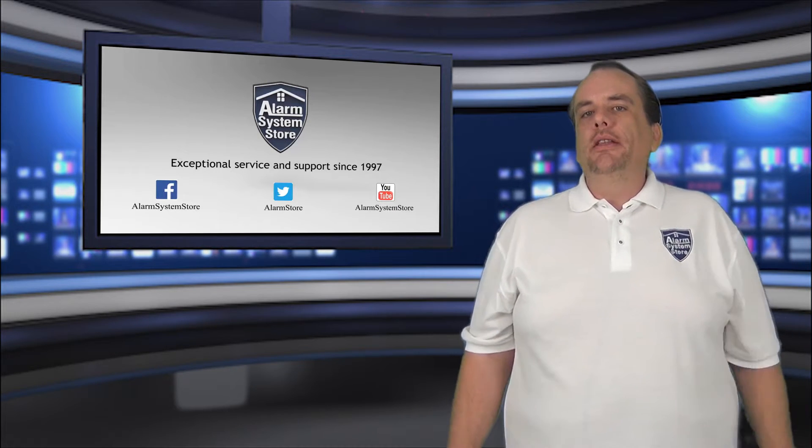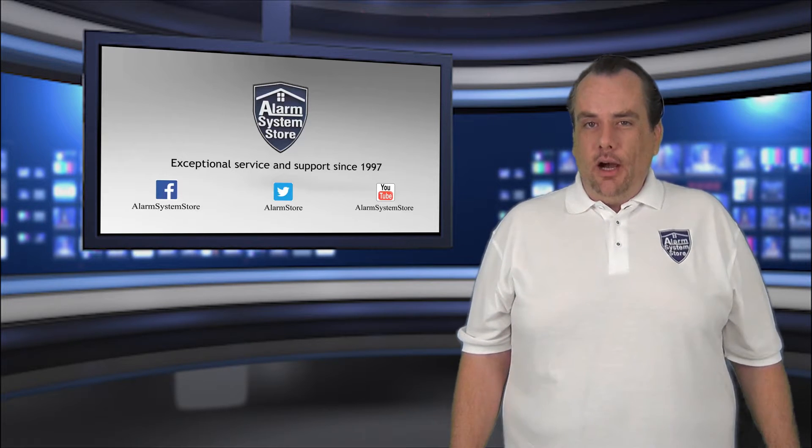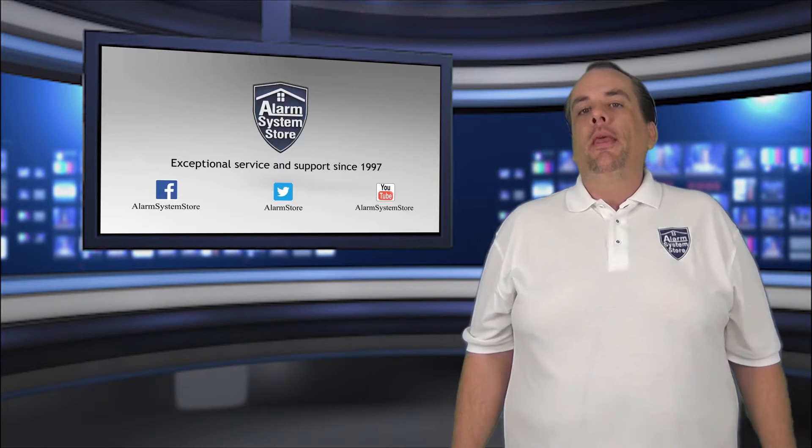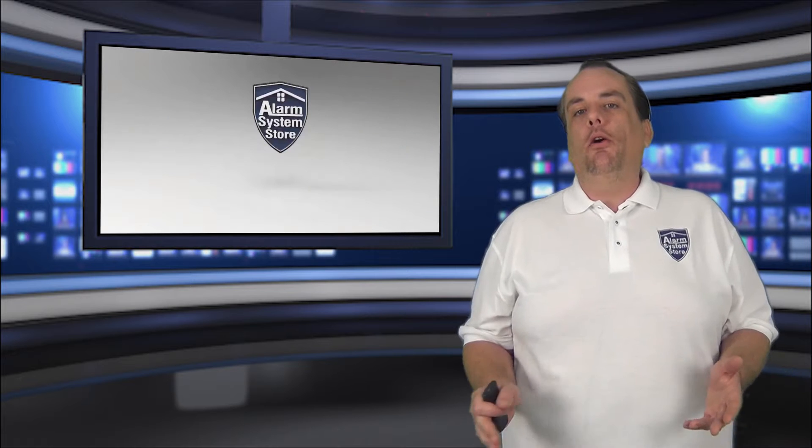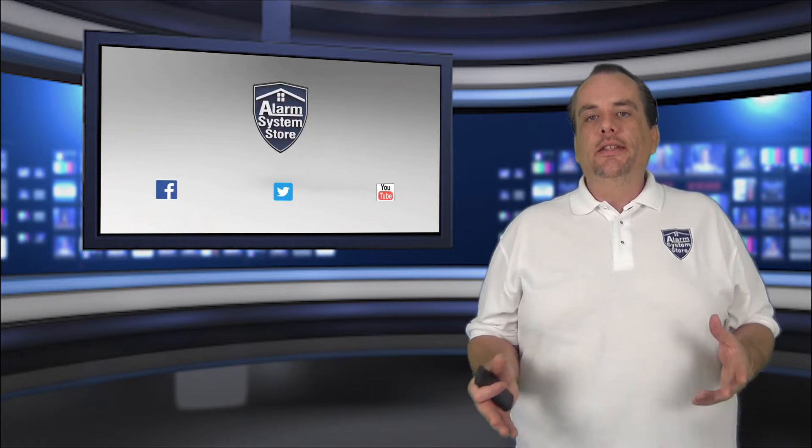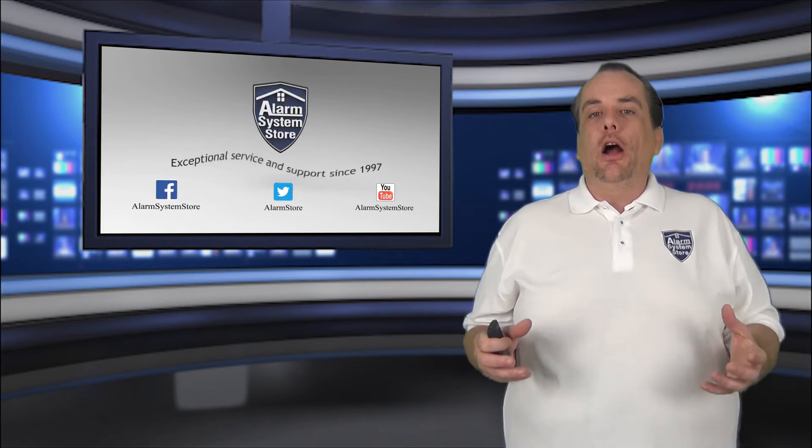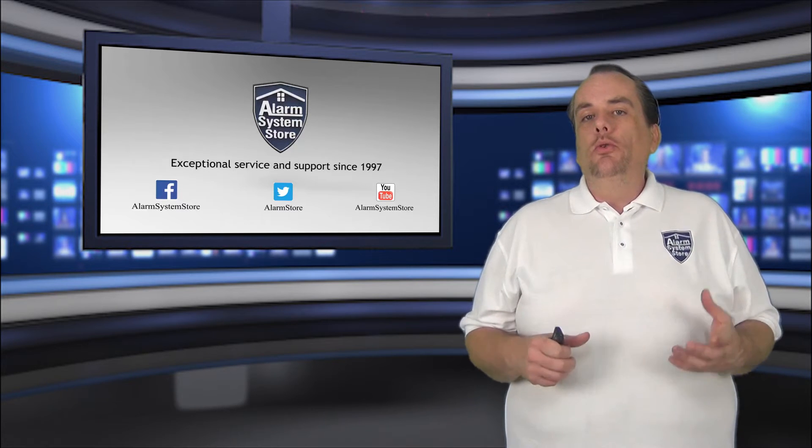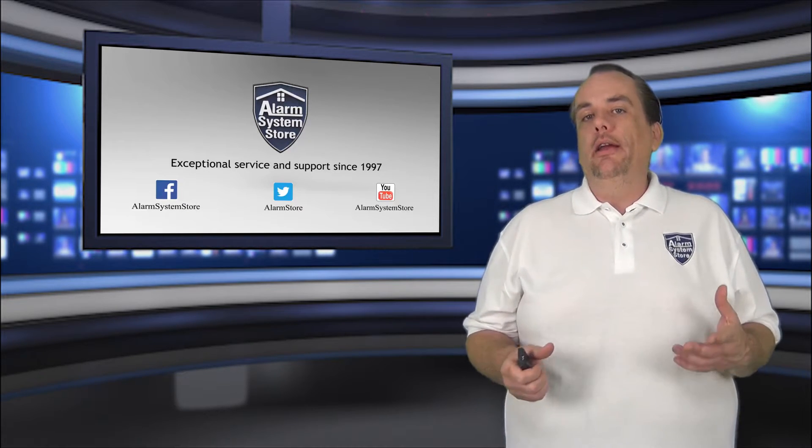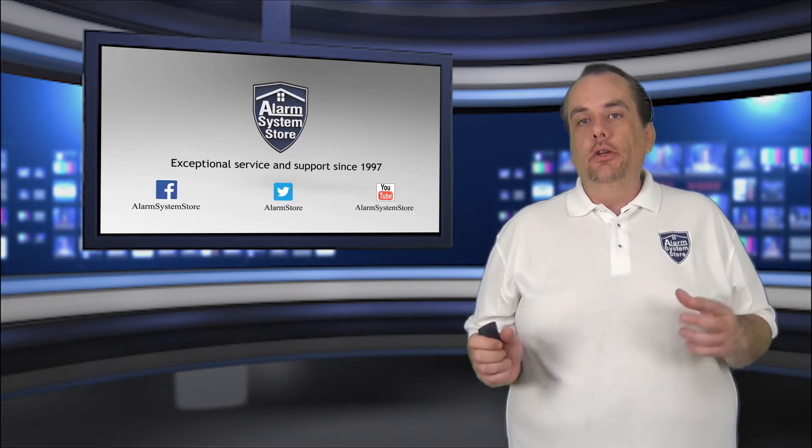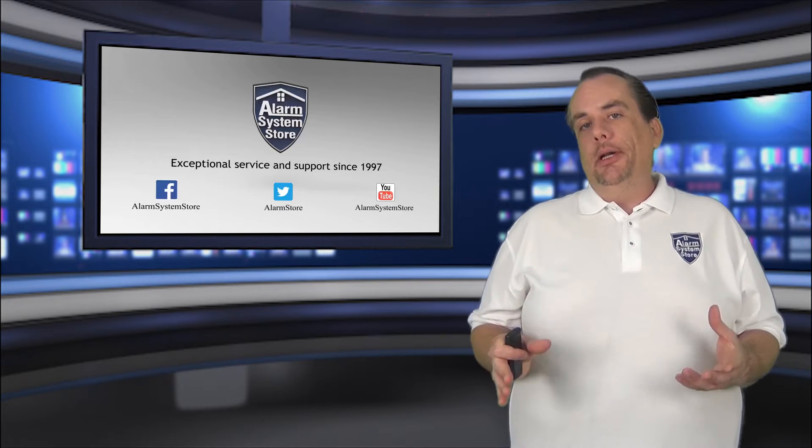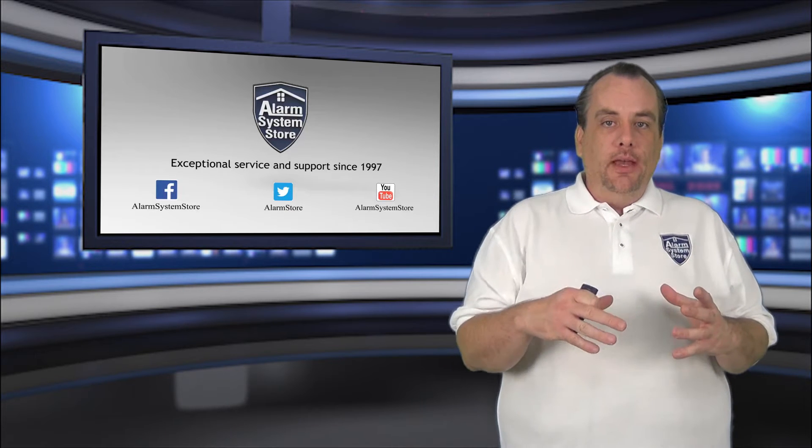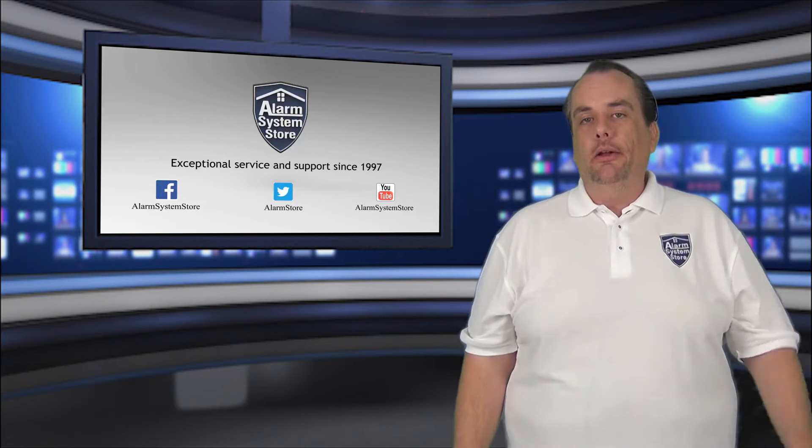They are the System Sensor smoke and carbon monoxide combination units and you can get them in either two wire or four wire variety. What this does is it takes a smoke detector and a carbon monoxide detector and combines them into one unit and you also have to have an intermediary module to use these. So you will have the smoke and carbon monoxide detectors connected to a module and then the module will connect to your alarm panel.